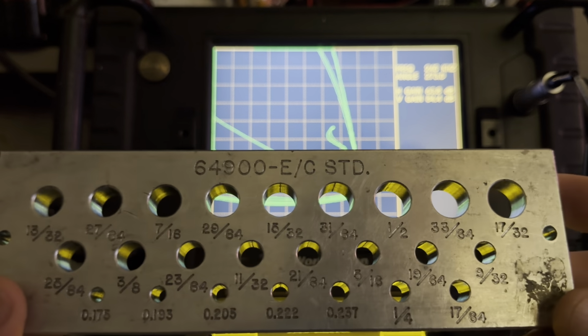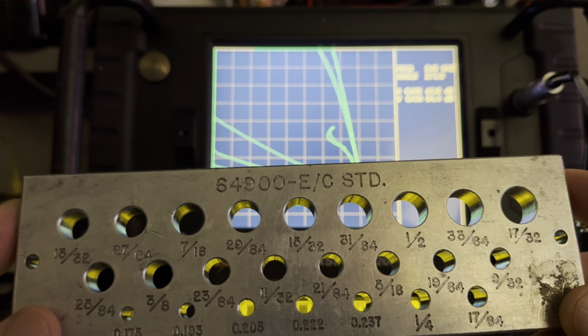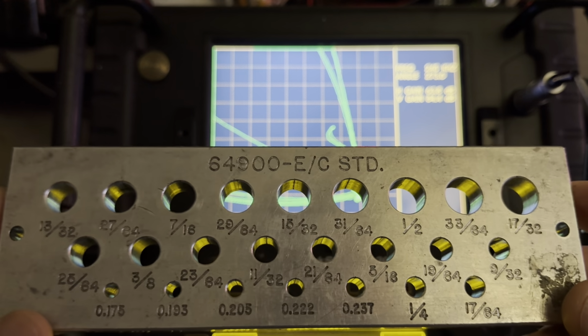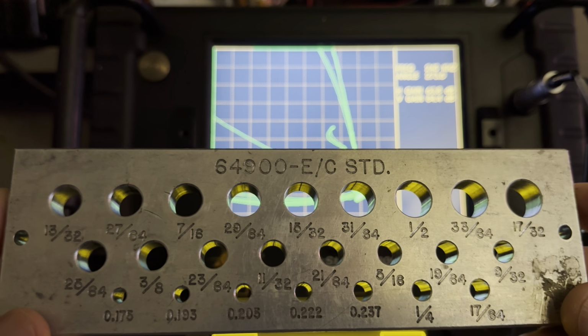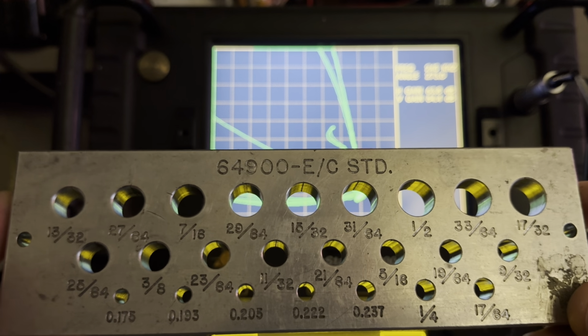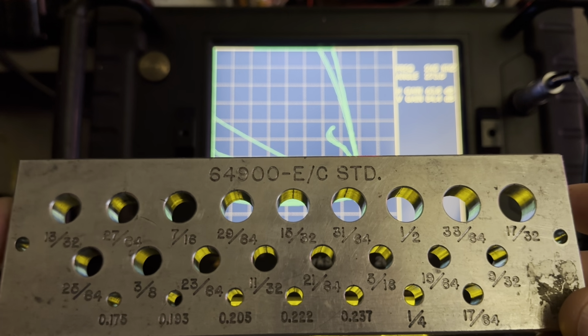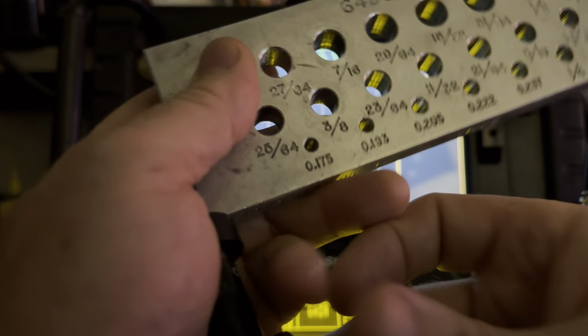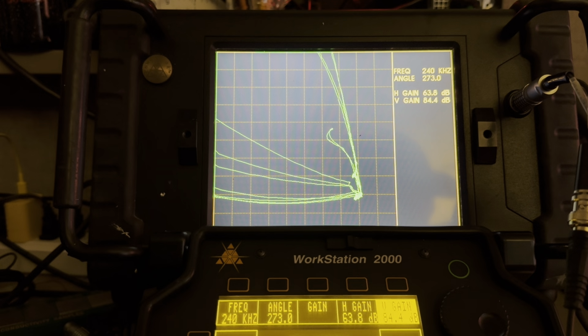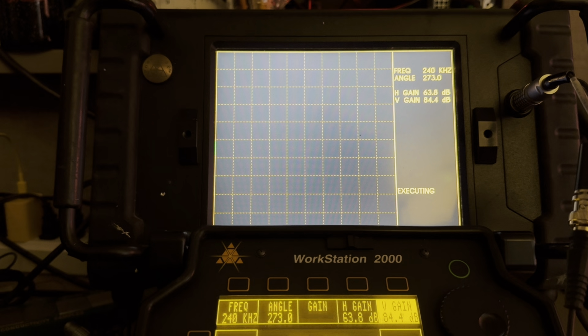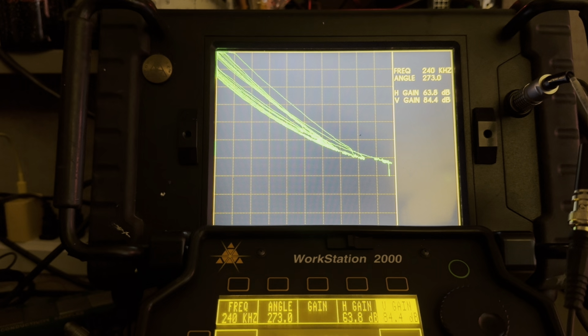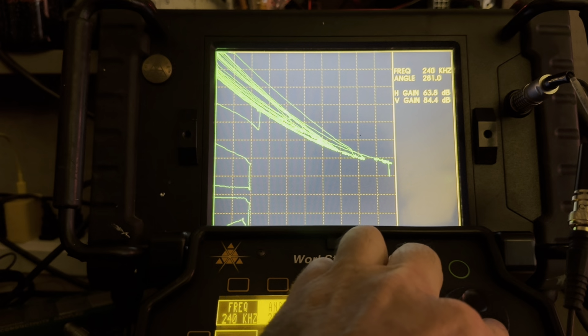Now you've got to keep in mind, the aluminum EDM block that I have and this block, although they're both aluminum, they may have some subtle differences, you know, chemistry-wise or heat treat-wise. But the noise or the probe motion may not be exactly vectored in the same manner. So how do we test that? I'm going to set this block down, and I'm just going to place the line on my probe down so the coil's facing the material. I will hit null to balance my impedance point. And when I lift off, you see how that lift-off trajectory is a bit off kilter by like 40 degrees? No problem. We're just going to rotate that down.